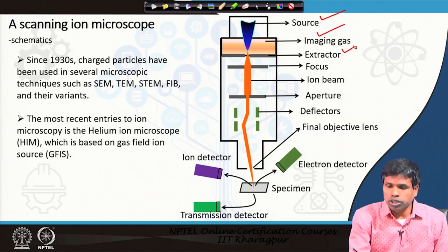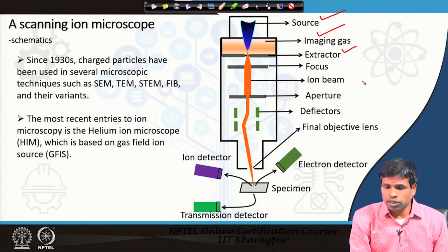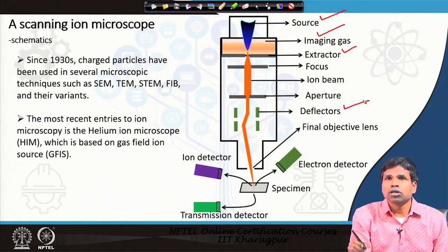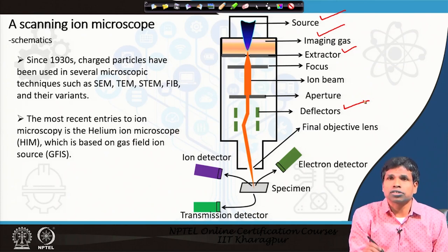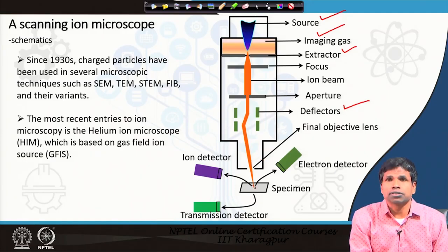Then the ion beam comes through, and we use different apertures — just as in the electron microscope, apertures are used to reduce the aperture angle and control the beam current. We also have deflector coils that allow us to scan the ion beam across the surface in a raster manner. Then we have the final objective lens, and the ion beam strikes the surface of the specimen.